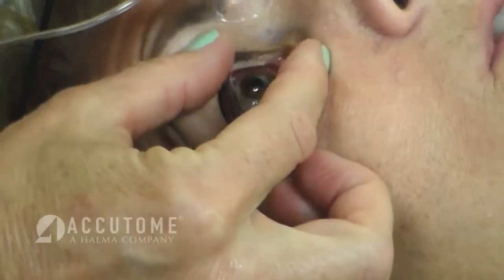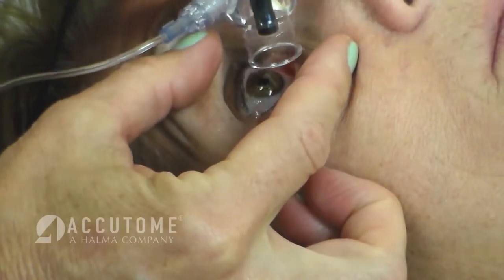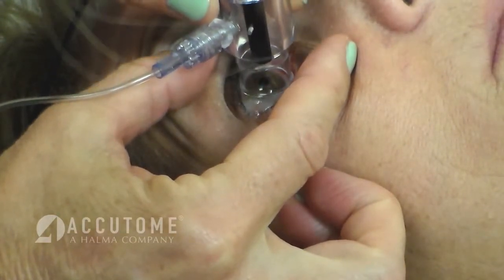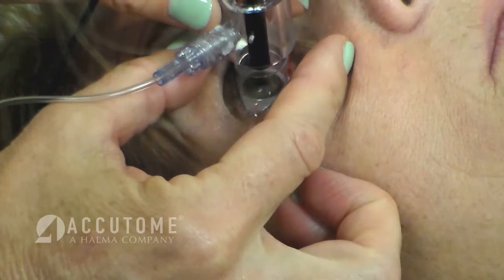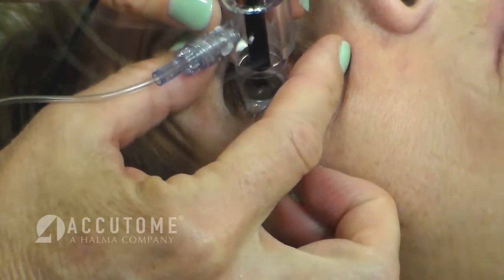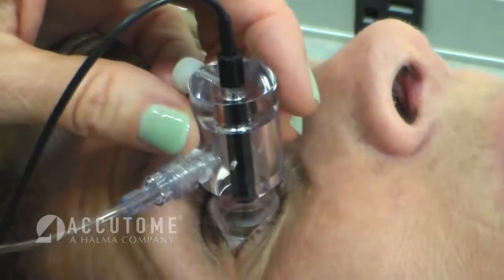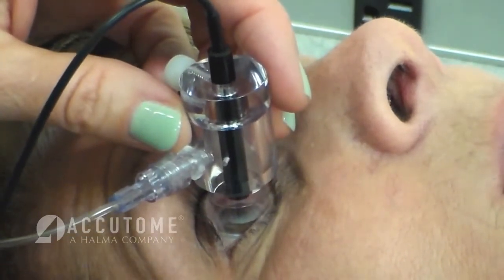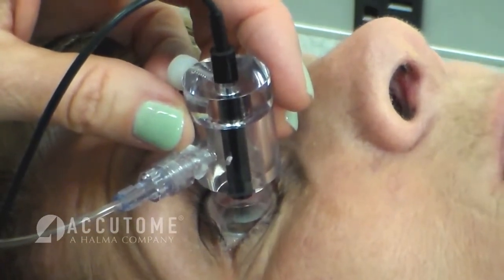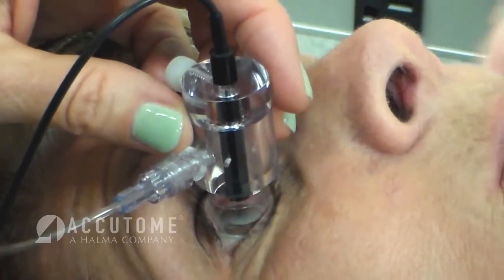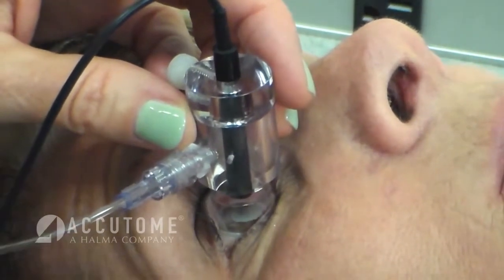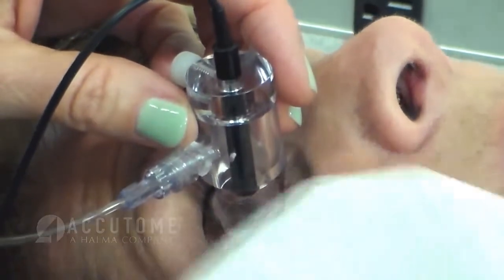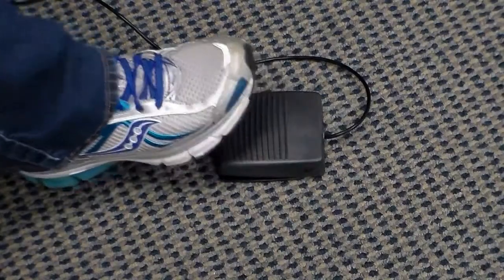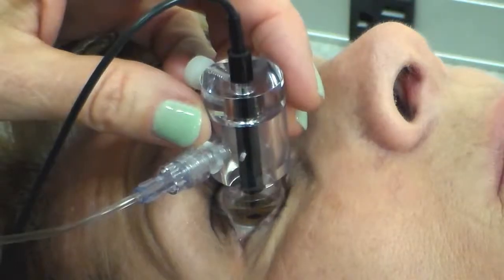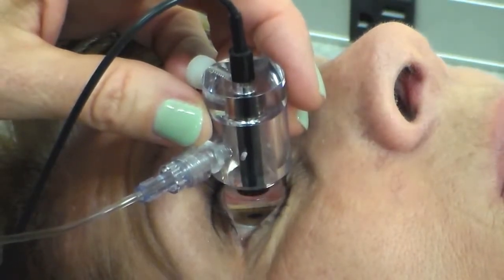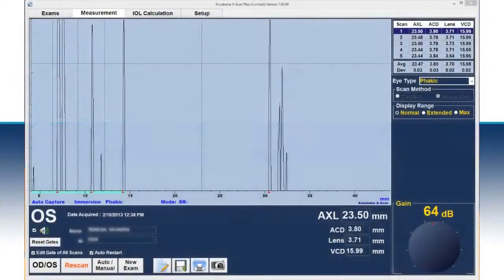With the patient reclined, ask them to fixate at a target on the ceiling and gently place the immersion shell into the patient's eye between the lids, ensuring that the shell is properly placed on the sclera and has no contact with the cornea. Once the shell is in place, release the upper and lower lids, allowing them to form a seal with a shell which retains the balanced salt solution and does not allow leakage. Press and hold the foot pedal and gently squeeze the balanced salt solution bottle until the fluid in the shell reaches the probe and a waveform appears on the computer screen.